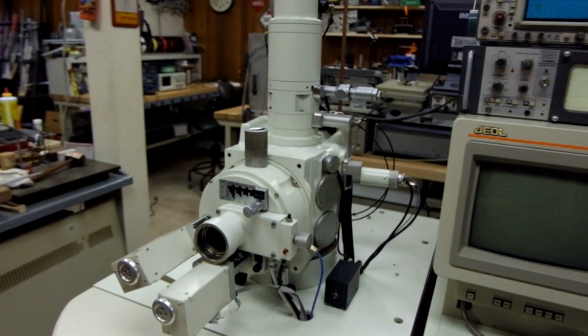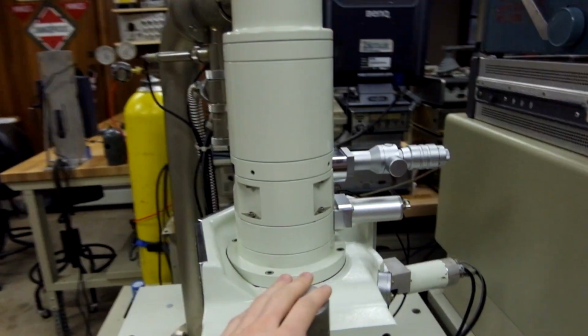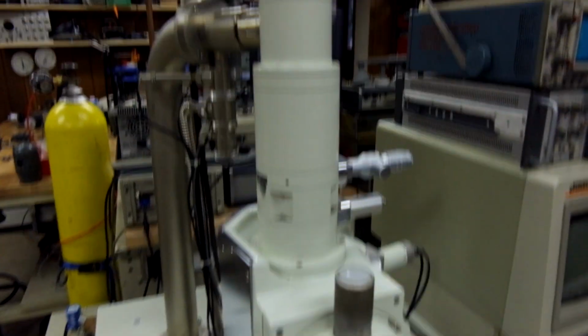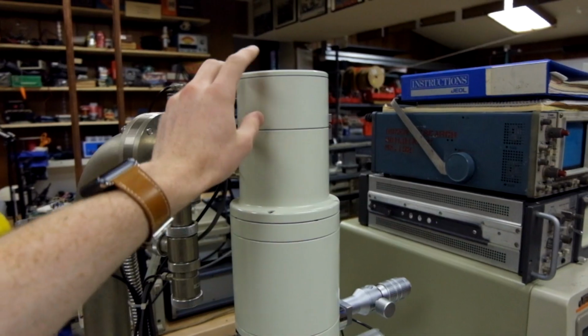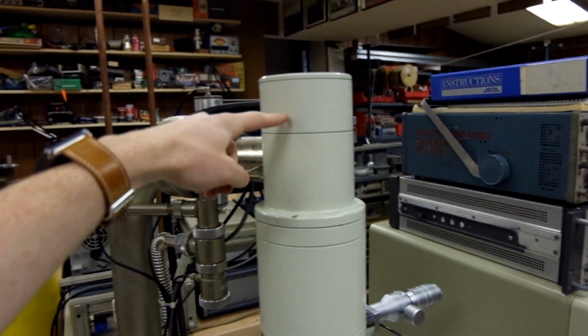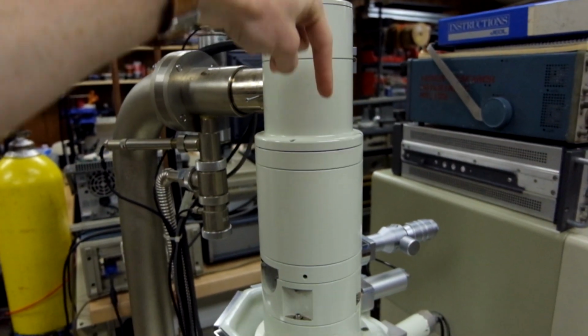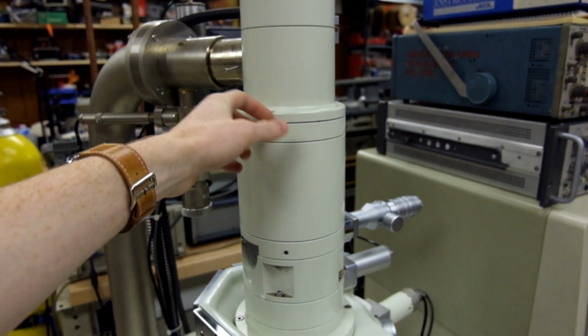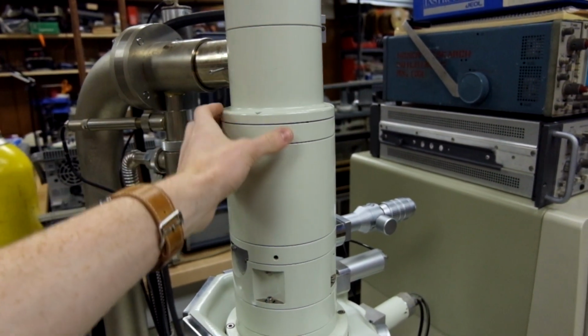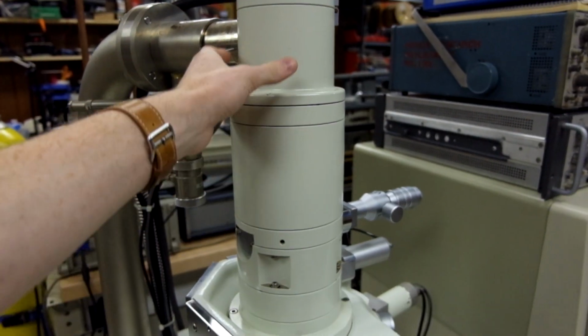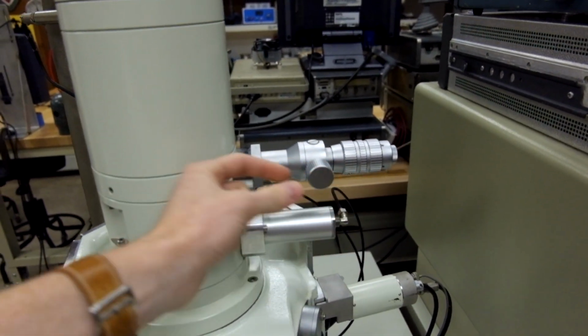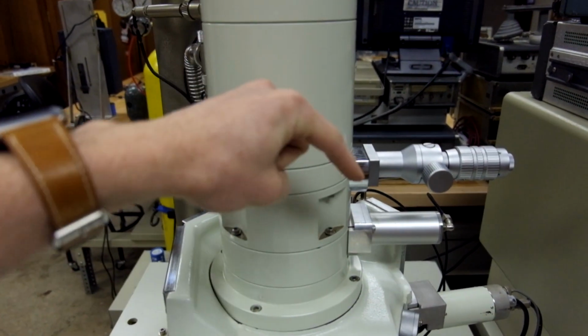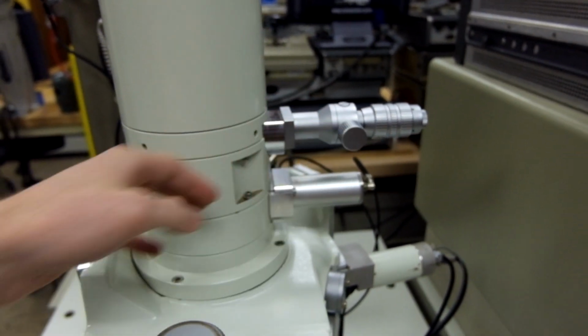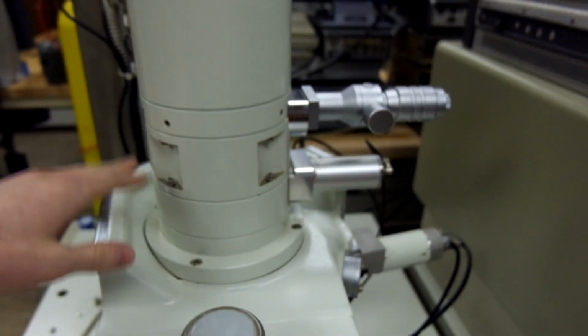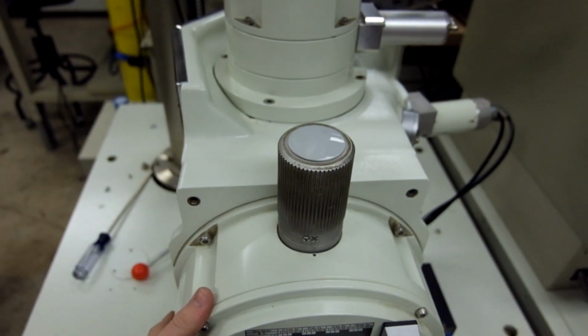And this is the column here, so this is the actual microscope. The whole thing is under high vacuum right now. The top part here has a little cap. This will pop open, that's where your filament goes. So this is the electron source, and the focused electron beam gets shot down here. There's tilt and shift coils, as well as focusing and stigmation coils, and there's an aperture right here, which consists of a very small piece of foil with small, like 50 micron-ish holes in it, and you can adjust and center that. And there's a gate valve here that separates this column from your specimen stage.